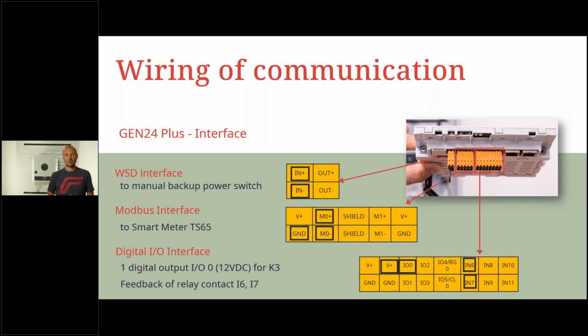And on the right hand side, this 16-pole plug, you get your feedbacks and your IO 0 for the K3 relay, and input 6 and 7 feedback from the contactors. That's it actually. So you need basically one communication cable, 8-pole cable, cat 5 or higher, from the inverter to the switchboard, and here you get your feedback. You connect your feedbacks from the contactors as well, K3, the small relay.